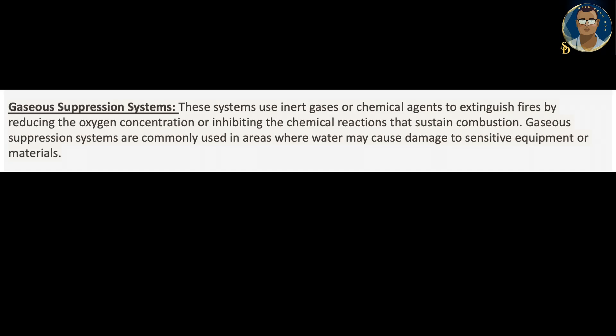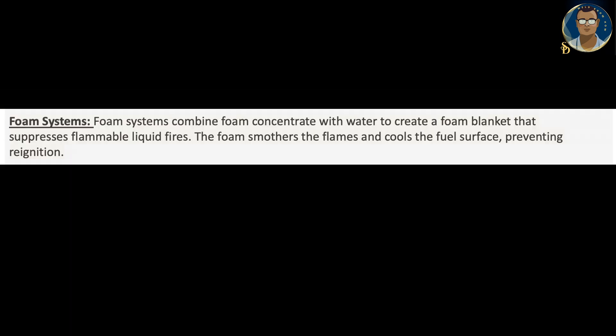Gaseous suppression systems use inert gases or chemical agents to extinguish fires by reducing the oxygen concentration or inhibiting the chemical reactions that sustain combustion. Gaseous suppression systems are commonly used in areas where water may cause damage to sensitive equipment or materials. Foam systems combine foam concentrate with water to create a foam blanket that suppresses flammable liquid fires. The foam smothers the flames and cools the fuel surface, preventing re-ignition.